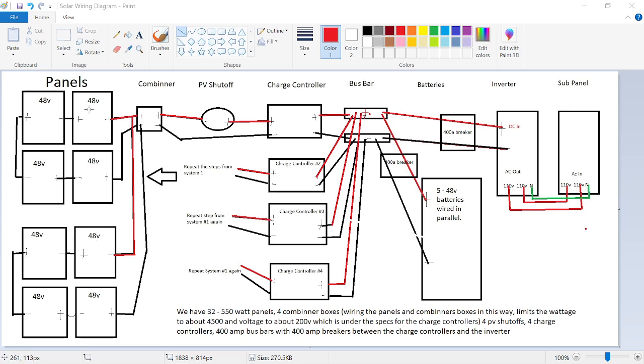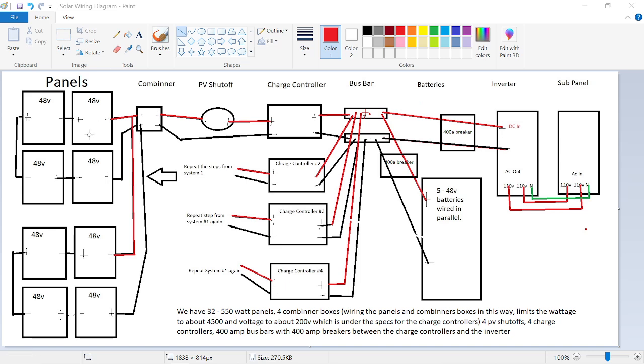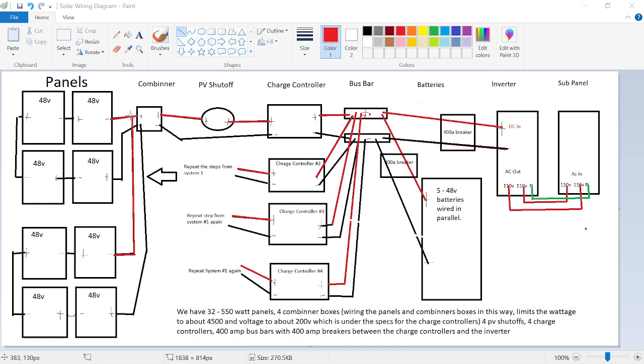And we repeated this process four times. So we come in to the panel, we run a jumper over to this one, jumper in between those. That is series. So you're basically seriesing those four together. Then we did the same thing down here. We series another four together, ran our lines, the PV wires, up to the one combiner box. So we have two inputs, two panel sets going into this PV combiner box.